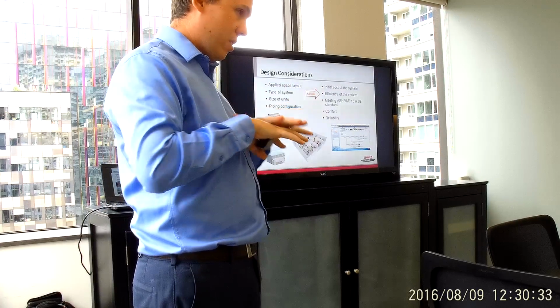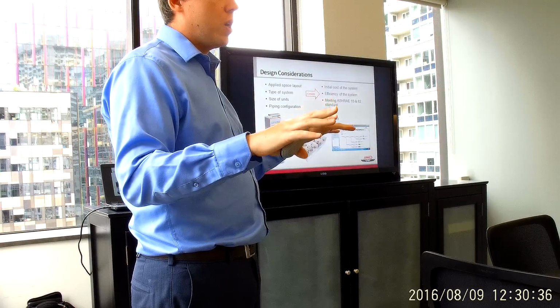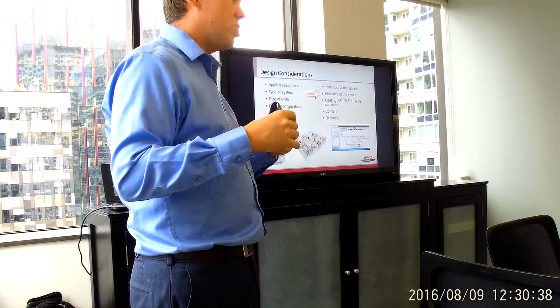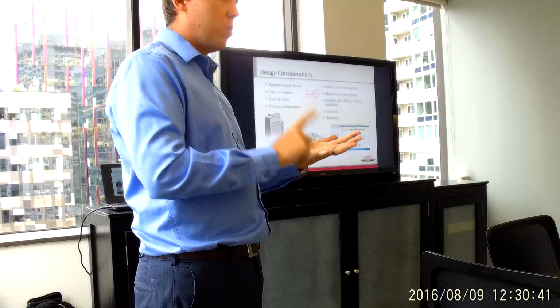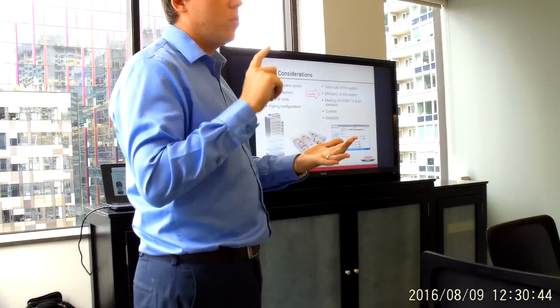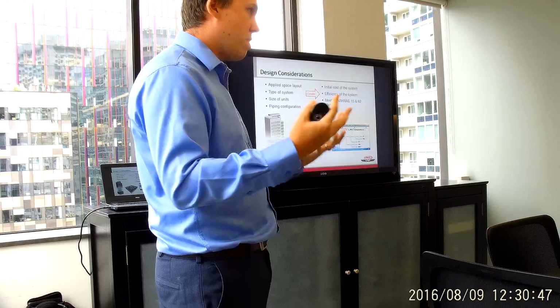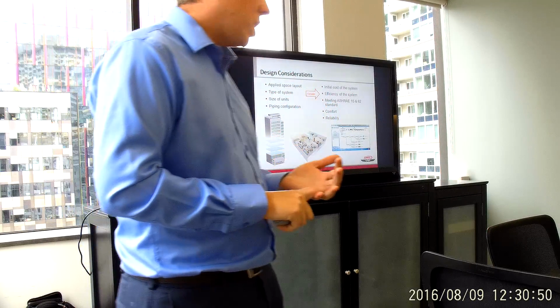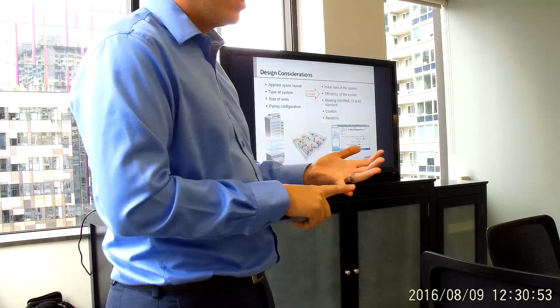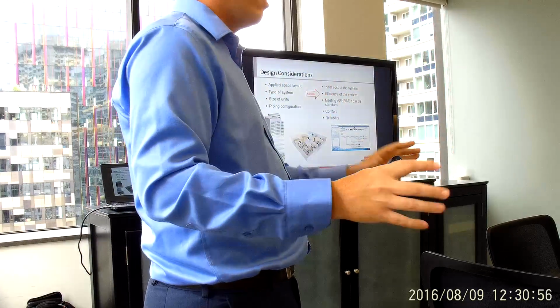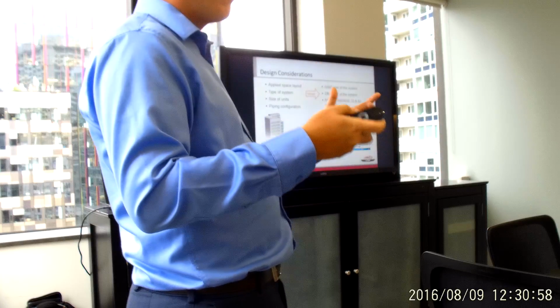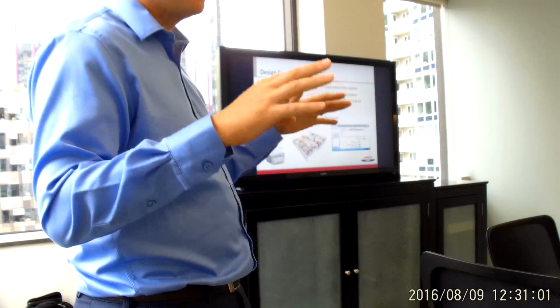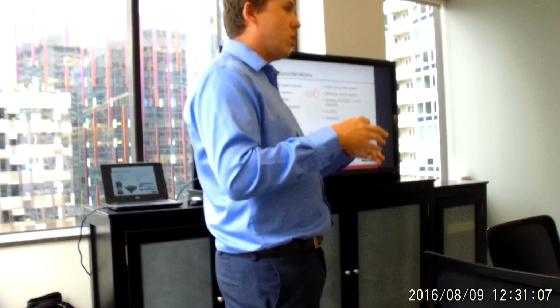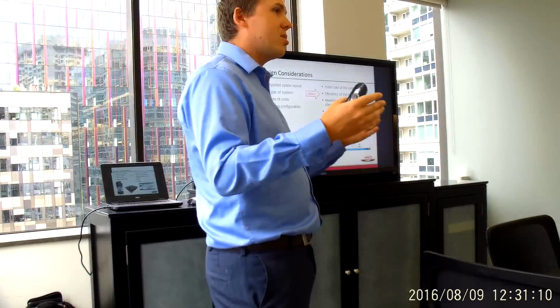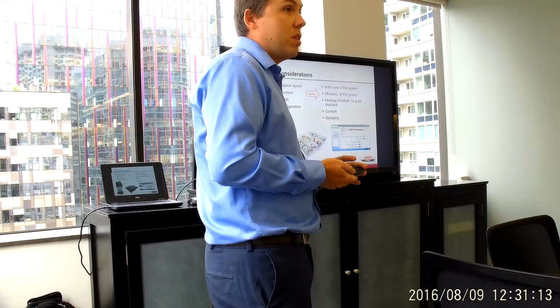You give us the indoor floor plates, the capacities associated with that, and we'll give you the calculations for each iteration. You can tell me you want to look at 36 ton, the biggest we've got - we know it's going to be fewer risers, simpler to install, and it'll operate fine at higher diversities. We can play around with those combination ratios. Or you want to go with just a 12-ton system on a single outdoor unit, very straightforward. Bearing in mind we've got billing, so full indoor unit, individual tenant billing with our system - that's why we use it on a residential basis. It's not prorated to square footage, it's actual consumption-based billing. We'll get to that when we get to the controls.